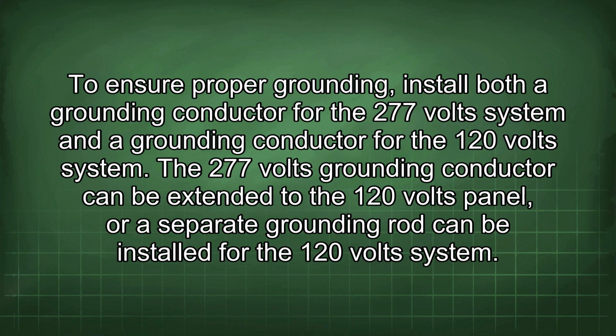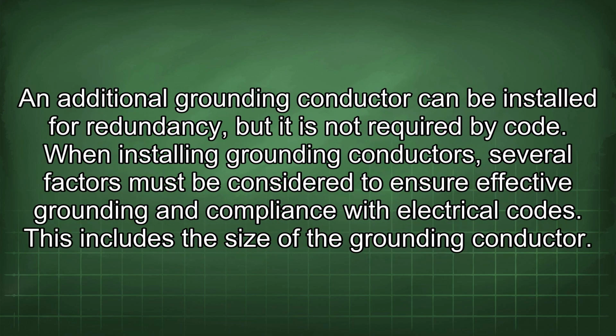To ensure proper grounding, install both the grounding conductor for the 277 volt system and a grounding conductor for the 120 volt system. The 277 volt grounding conductor can be extended to the 120 volt panel, or a separate grounding rod can be installed for the 120 volt system. An additional grounding conductor can be installed for redundancy, but it is not required by code.